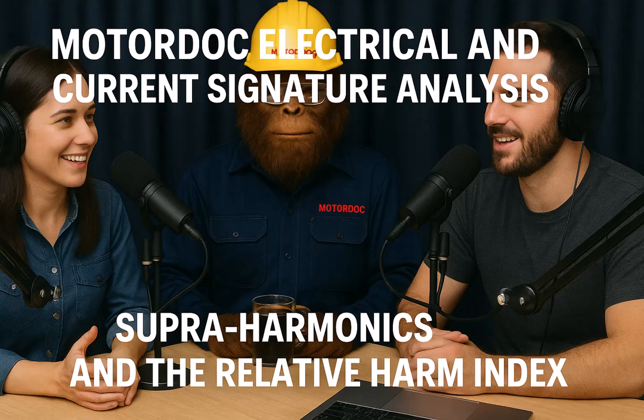And this issue of high ground currents, supra harmonics, it's not just wind turbines, is it? Absolutely not. The turbine examples are stark, but high ground currents and supra harmonic damage can happen anywhere. You have VFDs, power electronics. So industrial plants, commercial buildings. Yeah. Same potential problems: bearing fluting, insulation stress, electronic glitches. It's becoming a much broader issue across many sectors.